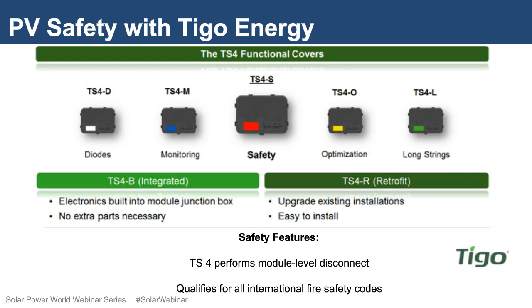Solectria is pleased to announce our compatibility with Tigo Energy's TS4 platform. The TS4 platform, module-level electronics, includes a family of devices that are either pre-integrated with the module or can be supplied as a retrofit in a separate junction box that's installed separately to the module. This family of products has a variety of feature sets which can be deployed selectively depending on the requirements of your specific array. Most notably, the TS4S model is a safety switch which allows you to meet module-level shutdown.